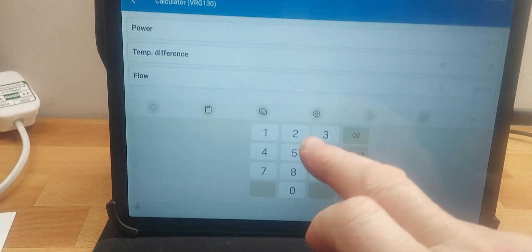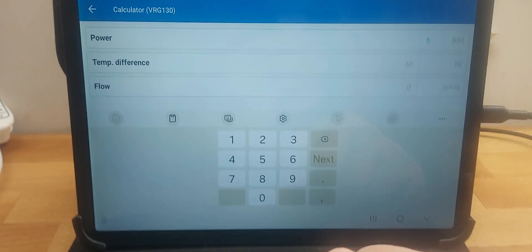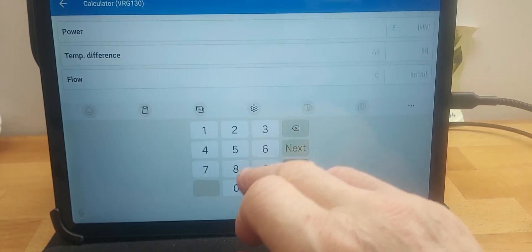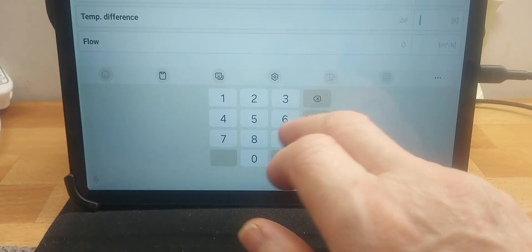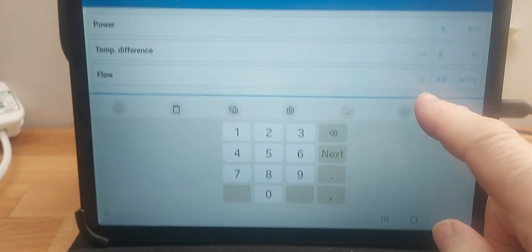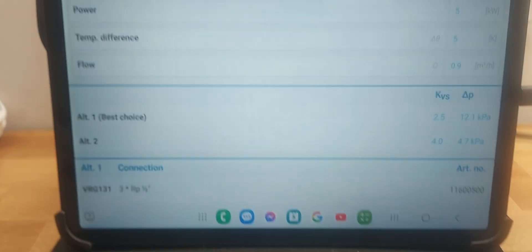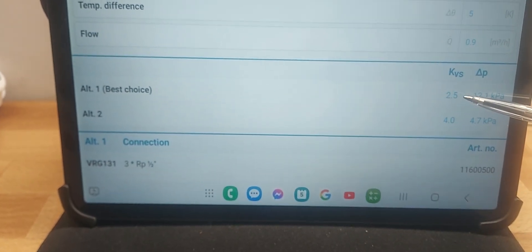Let's say I've got a circuit that's carrying five kilowatts. Here we've got the temperature difference, or delta T - let's say we're going to do underfloor, so five kilowatts, delta T five. It's going to give us our flow rate and make some other assumptions for us, such as the pressure drop. It's automatically assumed a pressure loss in our circuit of about 12.1 kilopascals and selected a kvs value of 2.5.